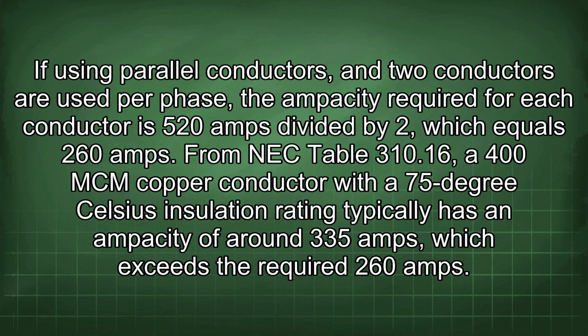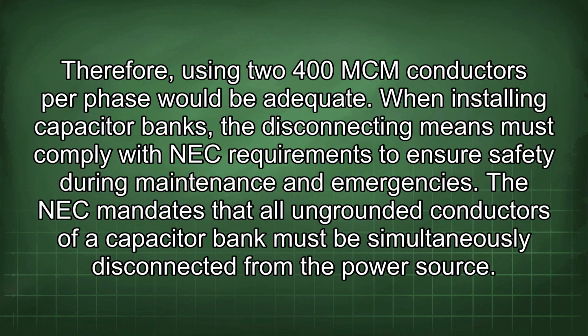If using parallel conductors, and 2 conductors are used per phase, the ampacity required for each conductor is 520 amps divided by 2, which equals 260 amps. From NEC Table 310.16, a 400 mcm copper conductor with a 75 degrees Celsius insulation rating typically has an ampacity of around 335 amps, which exceeds the required 260 amps. Therefore, using 2 400 mcm conductors per phase would be adequate.